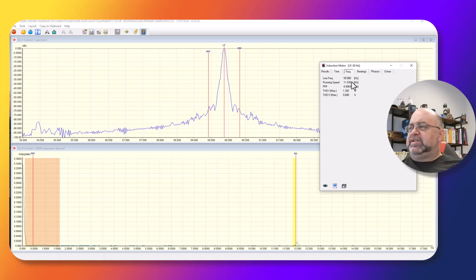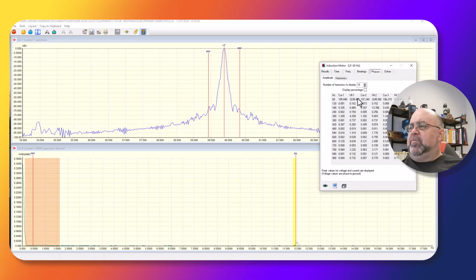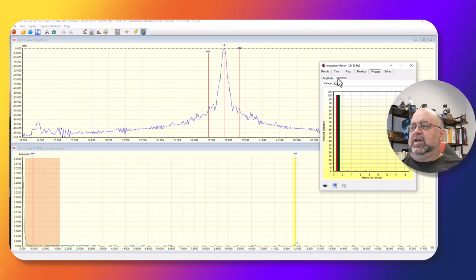Operating frequency, running speed, so there's the peak there. There are bearings in there, and looks like they're okay according to this. These are the harmonics, I've got it set to the 15th, it'll go out to the 50th, and voltage and current harmonics are very, very low.